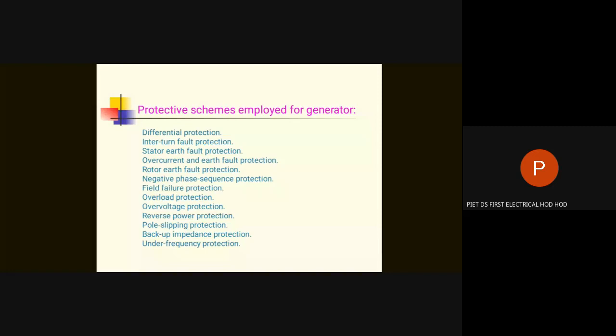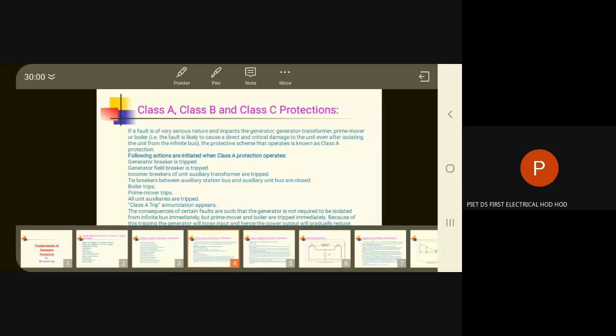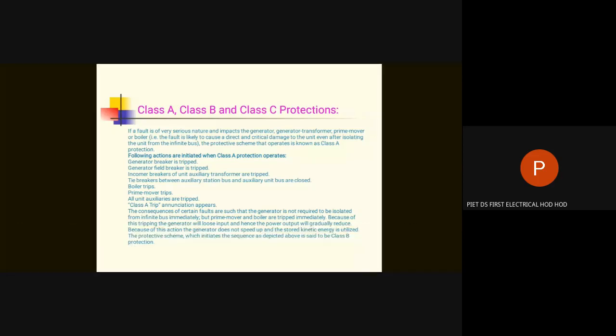So, as I was telling you, the different kinds of protections, as you can see on your screen, are class A, class B, and class C protections. The protective schemes are divided into three major classes. Class A is for very severe faults within the generator. Now I hope you know that the generator is connected to the generator transformer directly. Usually in a unit system of generation, there is no breaker between the generator and the generator transformer.